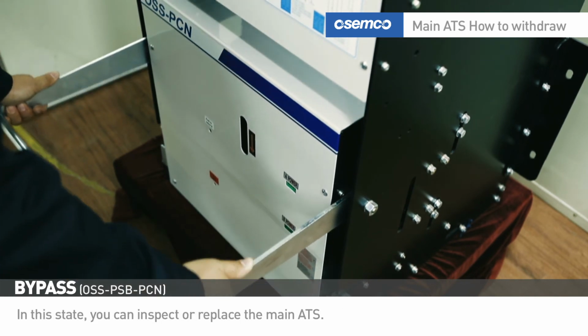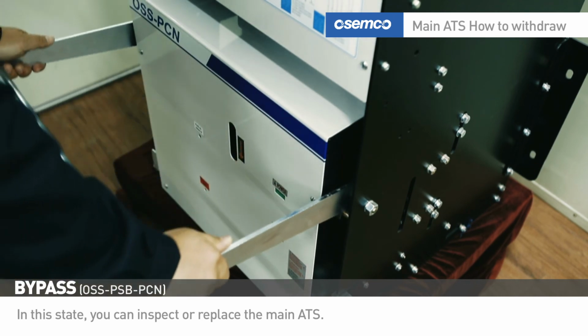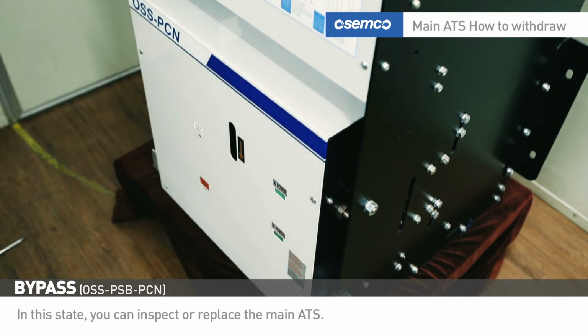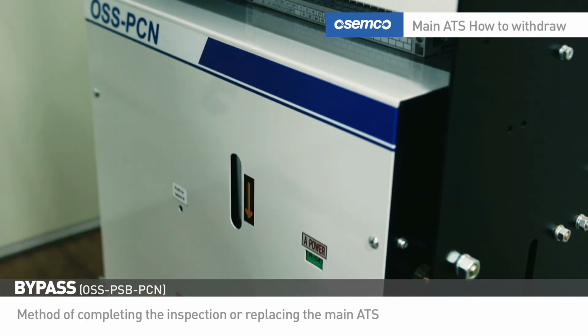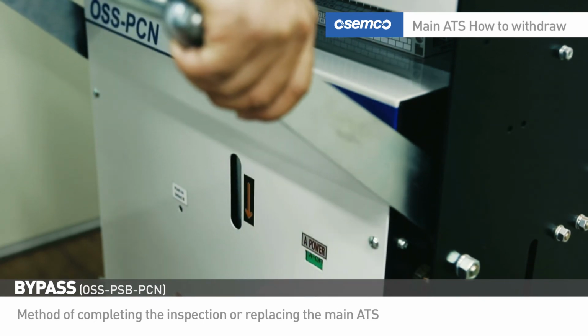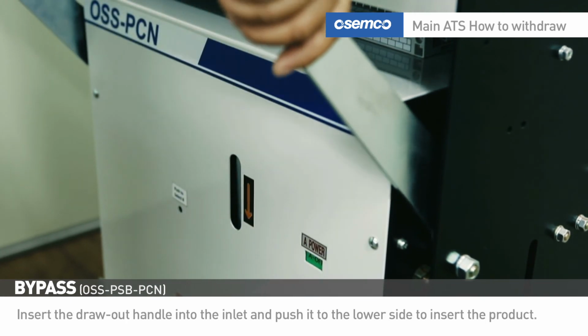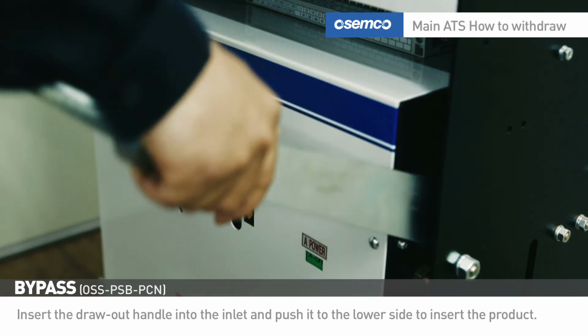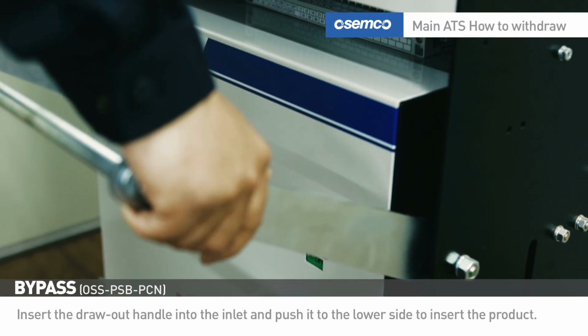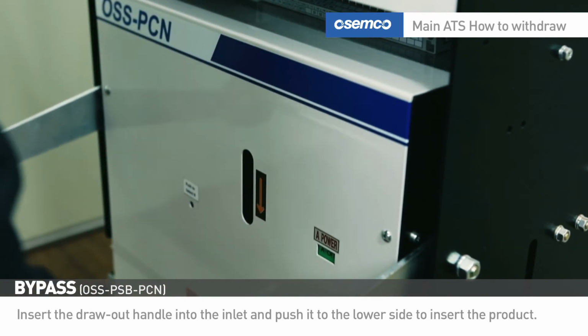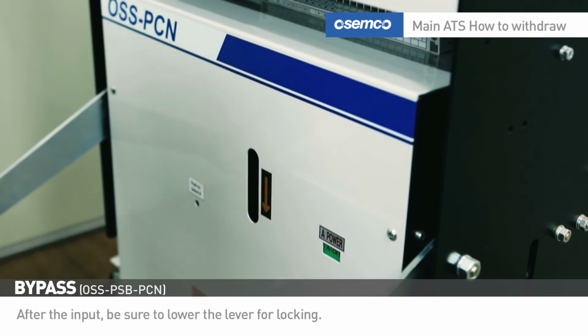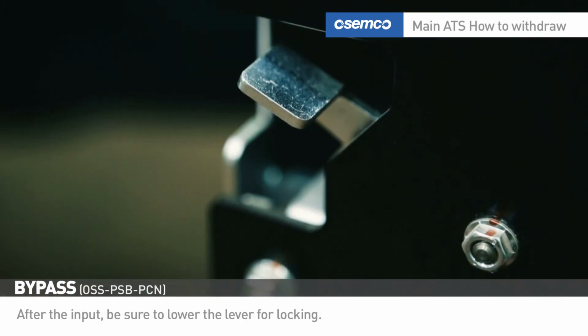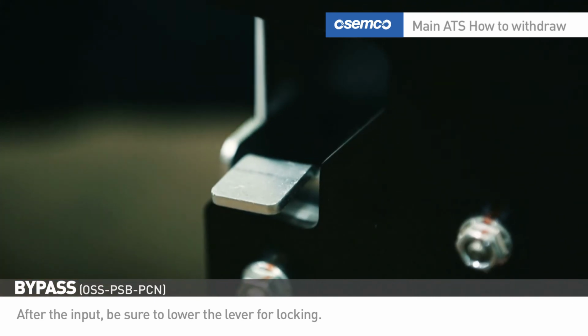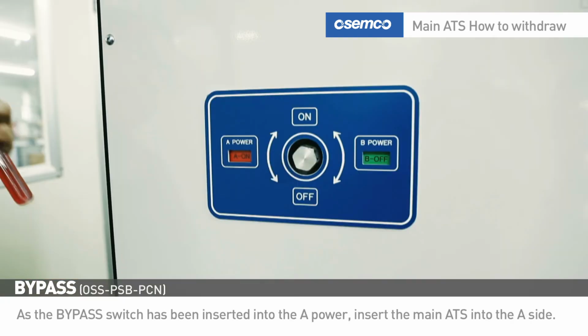In this state, you can inspect or replace the main ATS. Method of completing the inspection or replacing the main ATS. Insert the drawout handle into the inlet and push it to the lower side to insert the product. After the input, be sure to lower the lever for locking. As the bypass switch has been inserted into the A power, insert the main ATS into the A side.